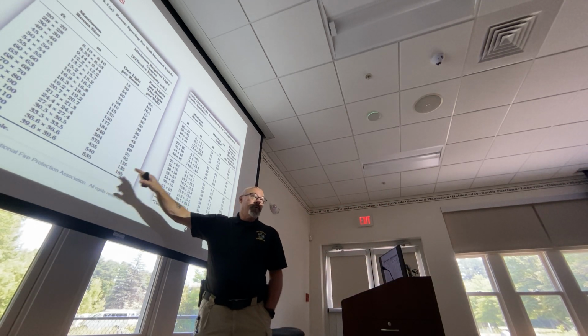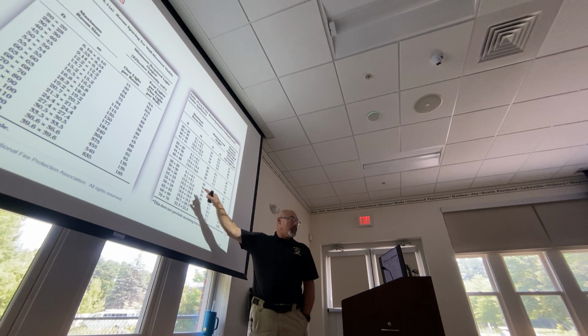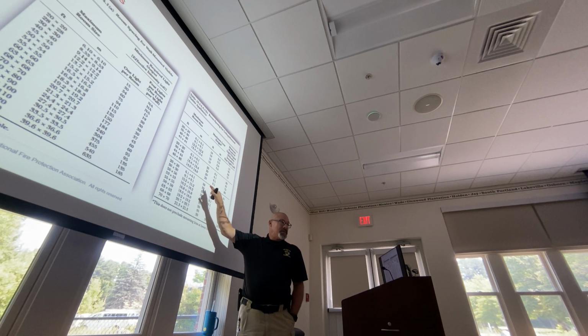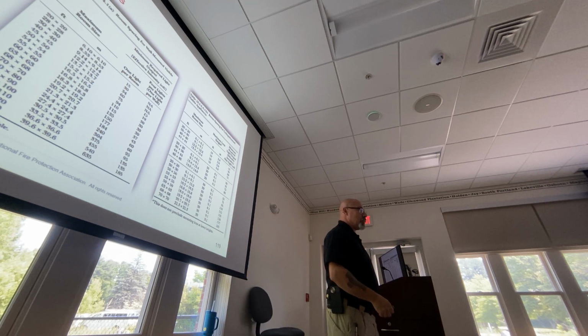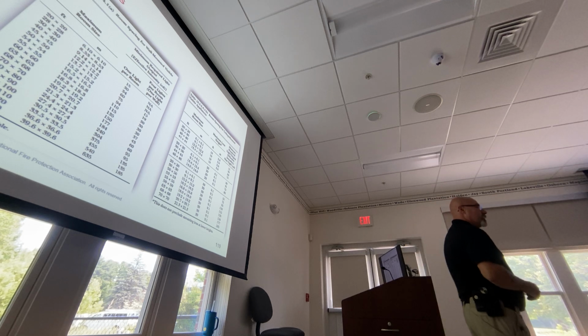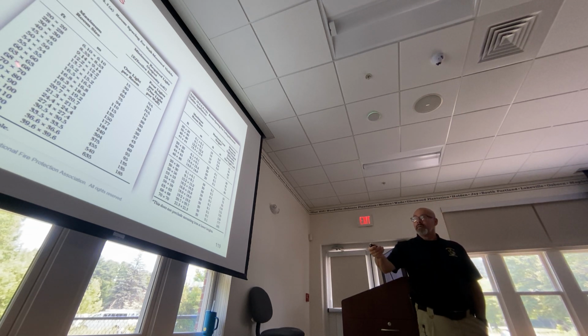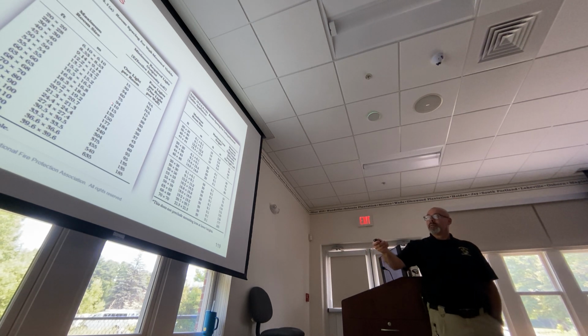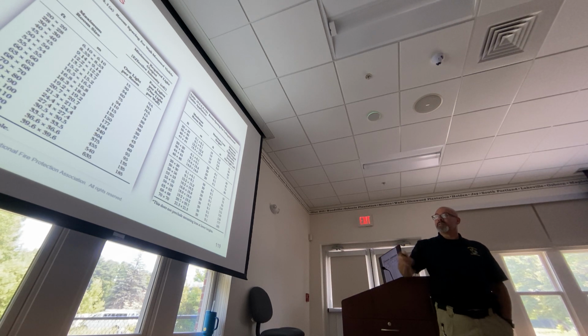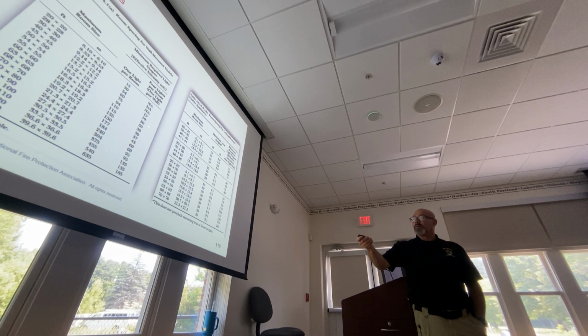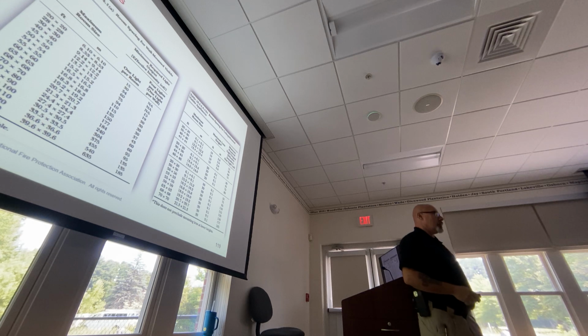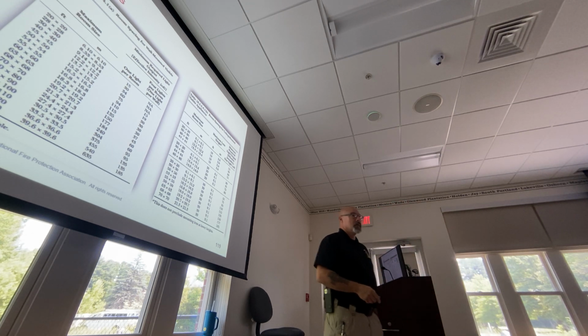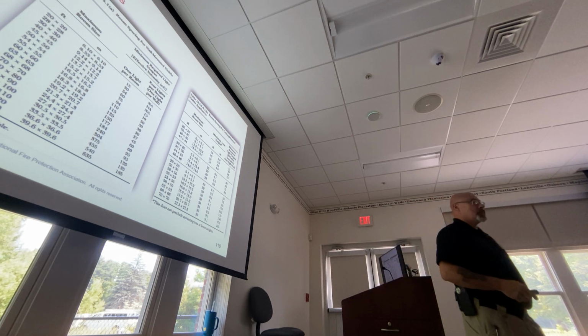Okay, so now you know how to read these tables, but these tables are important because you may have that same scenario. It's gonna say if you have a 50 by 50 room, what's the candela rating or the maximum height that the ceiling has to be for that 50 by 50 room if we're ceiling mounted. If we're wall mounted, 50 by 50, one light has to be at least 94 candela, or I have to have 4 30s in there. Okay? So we just need to know where to find that.